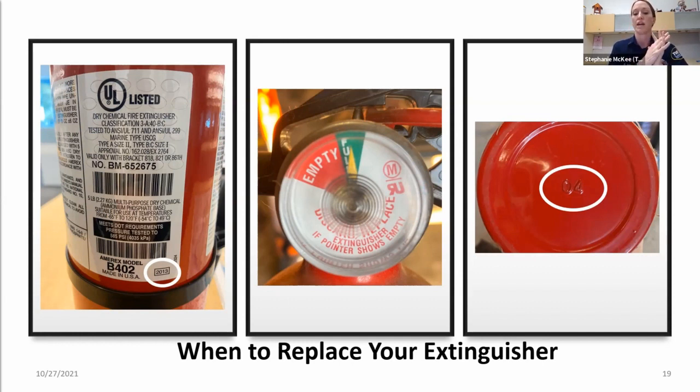You can get bigger fire extinguishers, and you can recharge those if necessary. By that, I mean what they call 5-pound fire extinguishers. The little small home ones that you would get at the grocery store or hardware store, the really small ones, are called home size. They have plastic tops on them and they are not rechargeable. Even some of the 5-pound or greater ones, I've seen some older 5-pound ones that have plastic tops. So plastic top ones can't be recharged, but the metal tops can if needed, and any of the fire equipment companies should be able to do that for you.